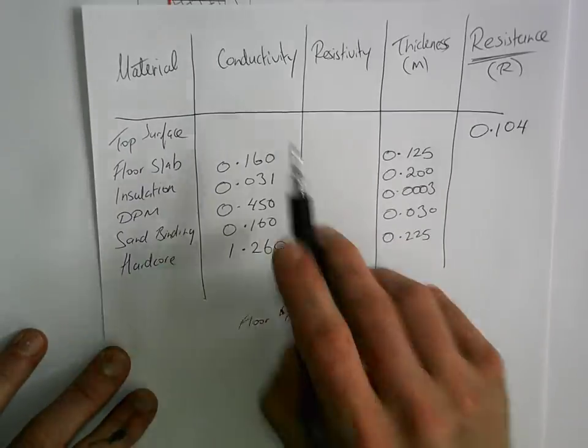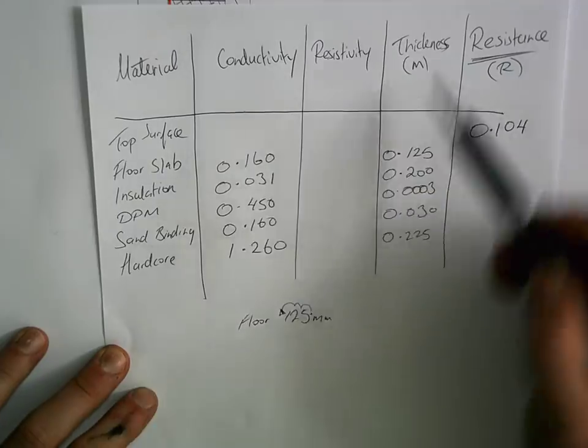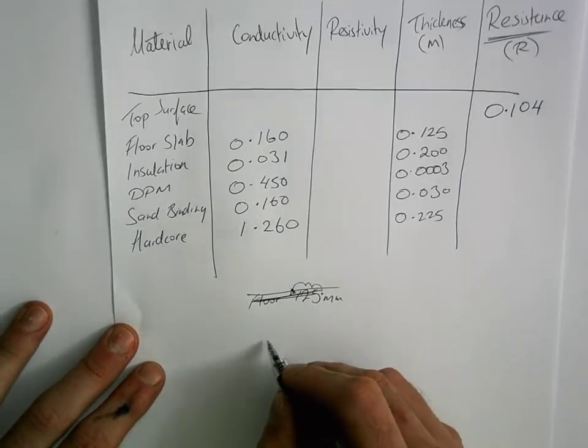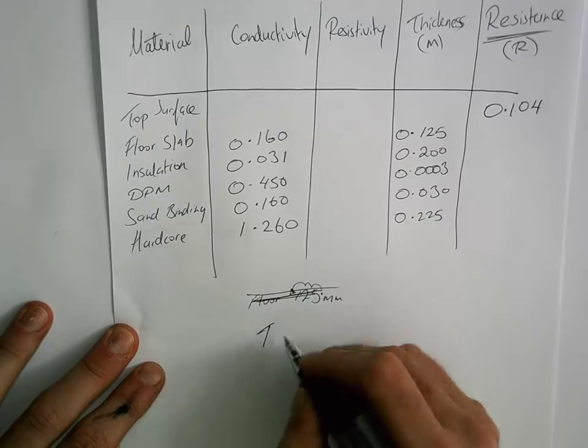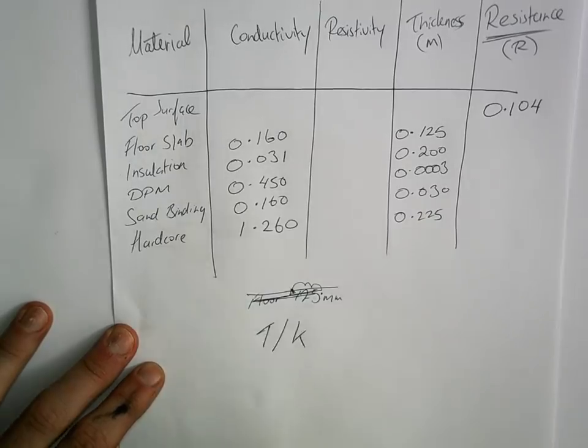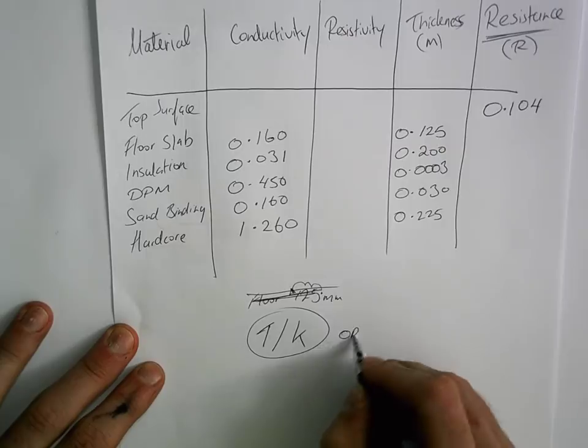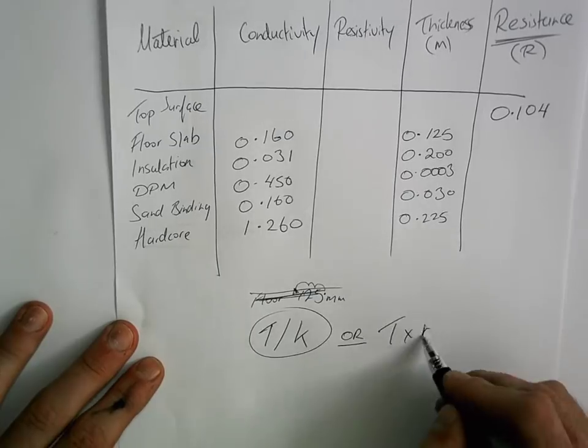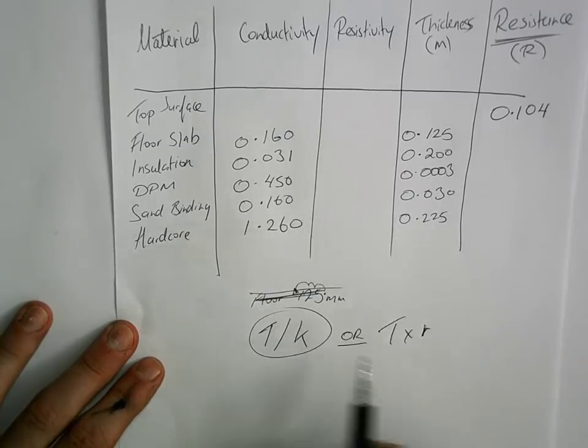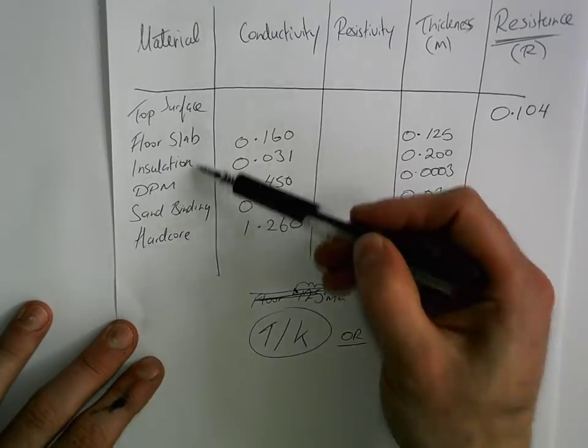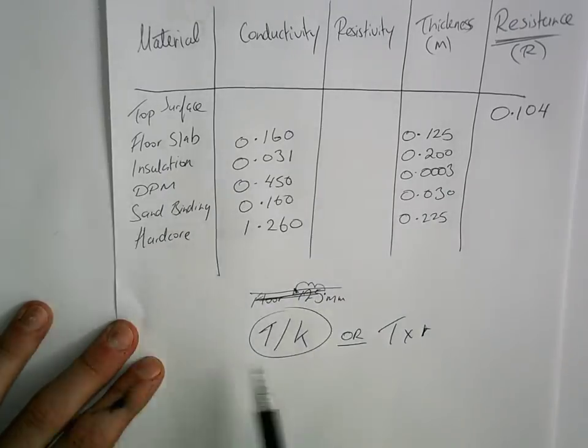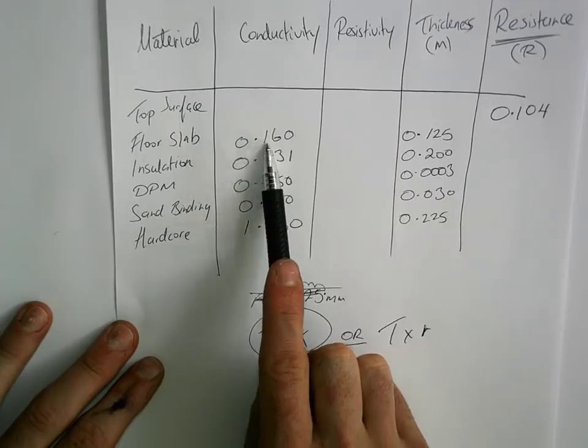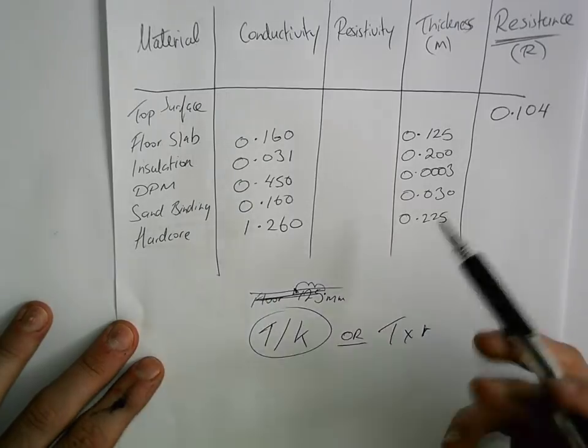Whether you're given conductivity or resistivity, you need the thickness to work out resistance. The formula is: resistance equals thickness divided by conductivity. That's the one we're using today. Alternatively, if you have resistivity, resistance equals thickness multiplied by resistivity — but that doesn't apply today. Learn off both formulas. For the floor slab, take thickness 0.125 divided by conductivity 0.160.